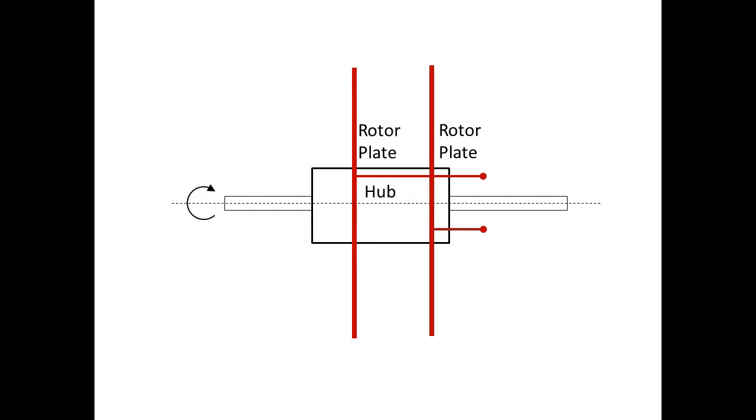This illustration highlights the basic structure and operating principle behind capacitive power coupler technology. Capacitive power couplers consist of rotor plates attached to a hub on a shaft, stator plates mounted in parallel to rotor plates with a small air gap between them, and drive electronics.